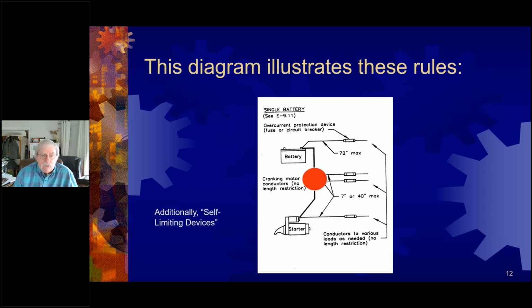I've been on board boats where the starter motors locked engaged, spun up, and created a dead short circuit in that primary cable that runs from the battery to the starter motor. And I can tell you that it's pretty scary when you've got 4-aught cable that's actually catching on fire, and you're in an engine room space trying to figure out how you're going to get this thing shut off. There's so much current flowing that the battery switch won't turn. You can't manually shut off any power. It's terrifying. That only ever happened once, but it stayed in my mind. So it's why I'm a fan of overcurrent protection in starter motor circuits, if it's practical.